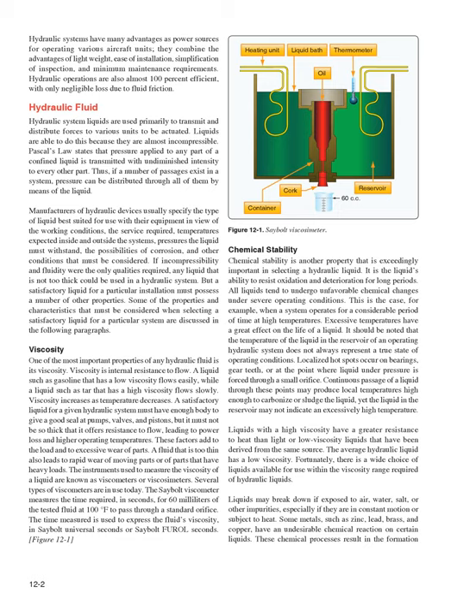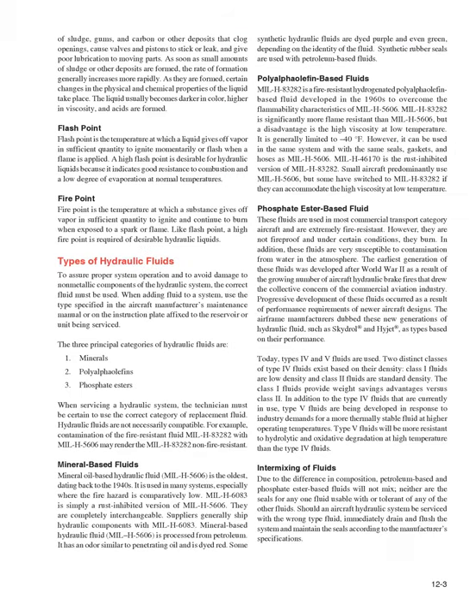Liquids may break down if exposed to air, water, salt, or other impurities, especially if they are in constant motion or subject to heat. Some metals, such as zinc, lead, brass, and copper, have an undesirable chemical reaction on certain liquids. These chemical processes result in the formation of sludge, gums, and carbon or other deposits that clog openings, cause valves and pistons to stick or leak, and give poor lubrication to moving parts.